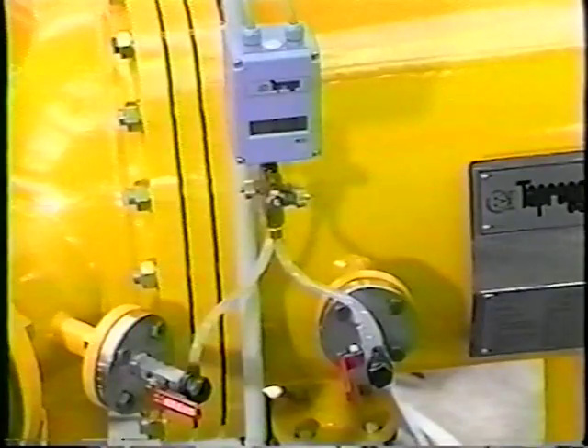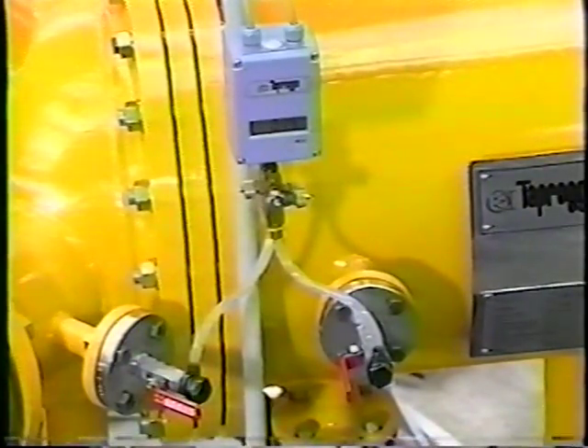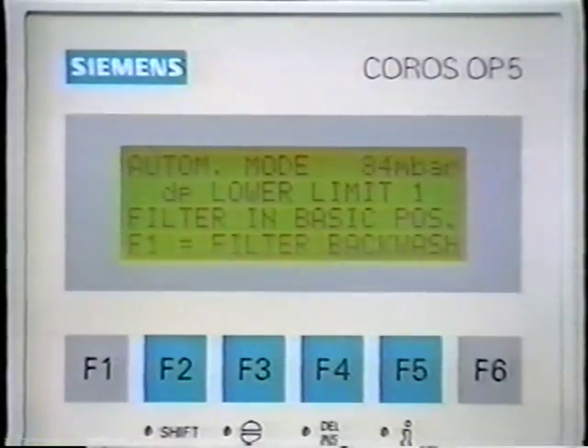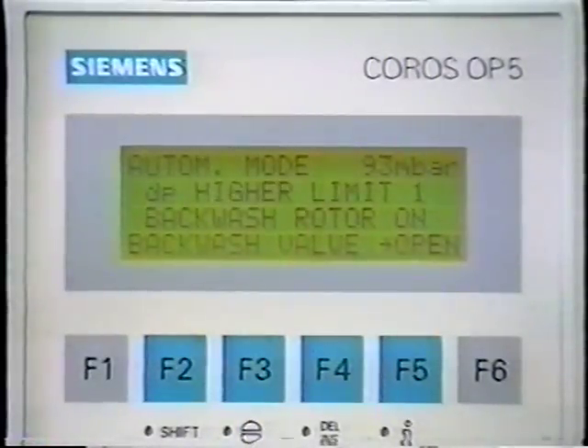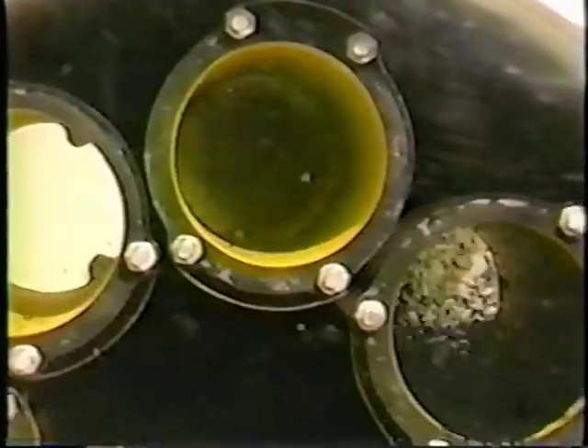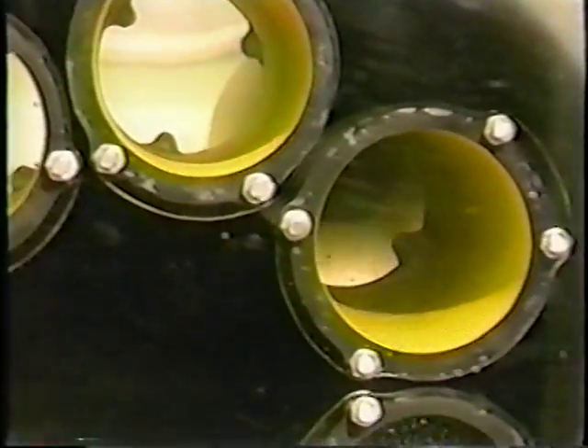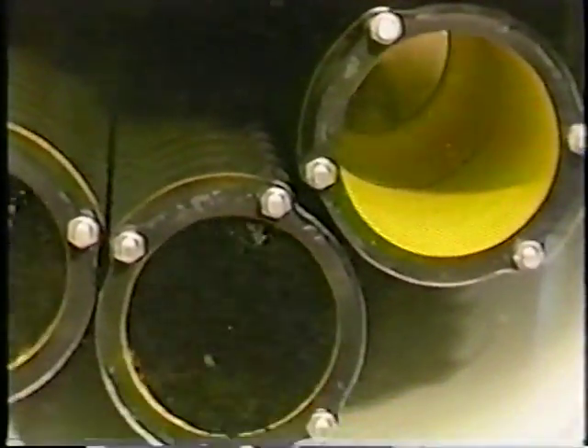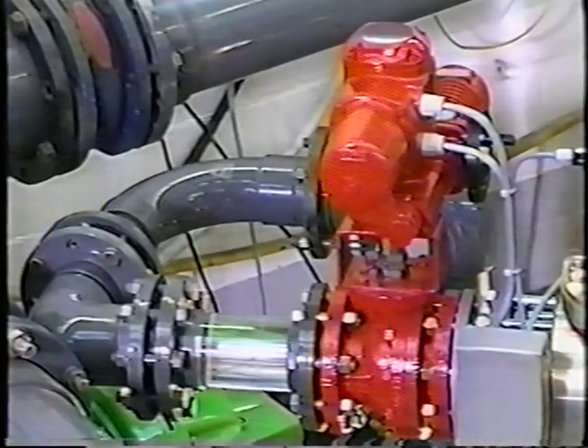The pressure lines of the differential pressure measuring system are connected across the clean and dirty side of the filter elements. The pressure differential across the filter element increases with the fouling. When a preset limit value is reached, the rotor begins to move and the valve of the backwash pipe opens. The flushing shoe, with its automatic spring adjustment, covers one filter cartridge at a time. The backwash water only flows through the filter cartridge from the outside to the inside, due to the pressure difference between the system and the end of the backwash pipe. The debris particles are flushed from the filter via the backwash pipe.